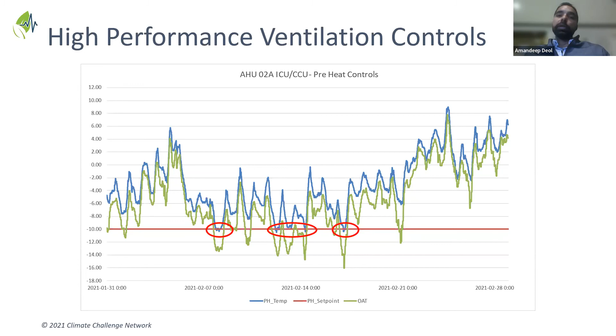Other observations that we noticed, and as the operator is currently working on optimizing this project further, is around static pressure or supply temperature reset. In this case, you could see that the -10 is your set point, your blue is your supply temperature, and your green is your outside temperature. Currently the supply temperature is following the outside pattern, which means there is a further opportunity within the system controls to reset the supply temperature to be controlled based on the load downstream. Which again will be further improved as JCI and the team work on making this hospital even better than it is right now.